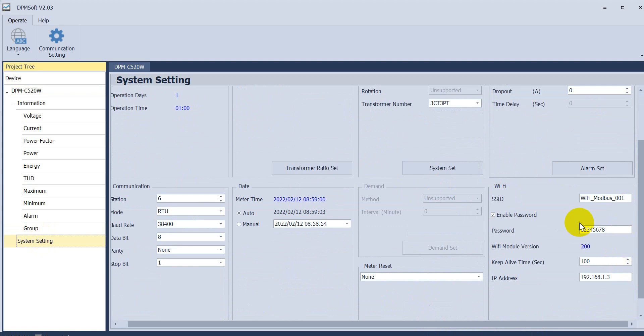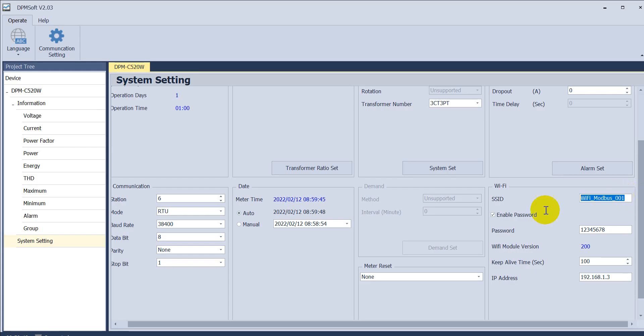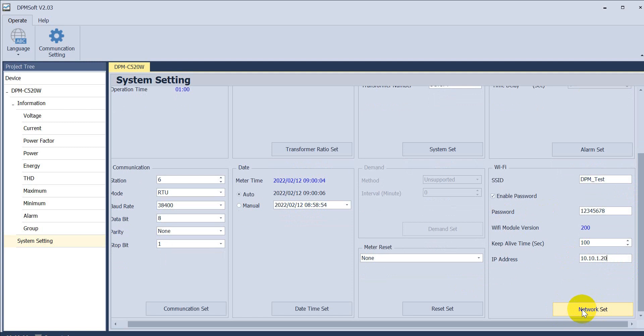Now we will try to modify the SSID and IP to another set. We will change the SSID to DPM_test, and the IP address parameter to 10.10.1.20, and the access point IP would be 10.10.1.6. After that, we can click network set. We modify the power meter SSID setting to DPM_test, change the IP address to 10.10.1.20, and then click network set.